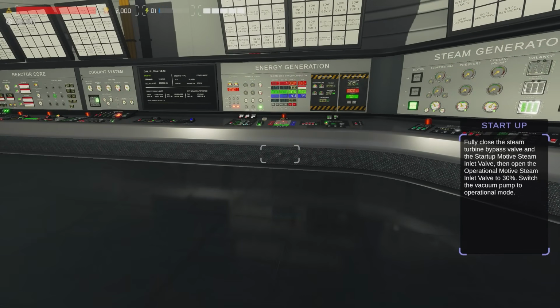Fully close the steam turbine bypass valve and the startup motive steam inlet valve, then open the operational motive steam inlet valve to 30%, switch the vacuum pump to operational mode.